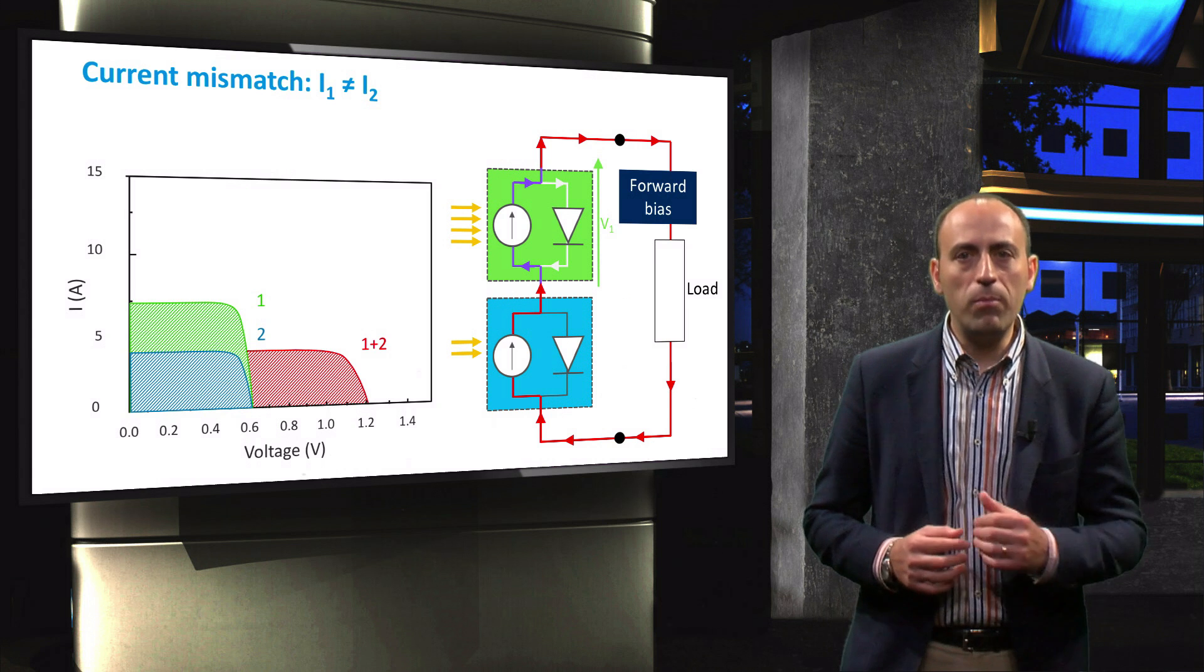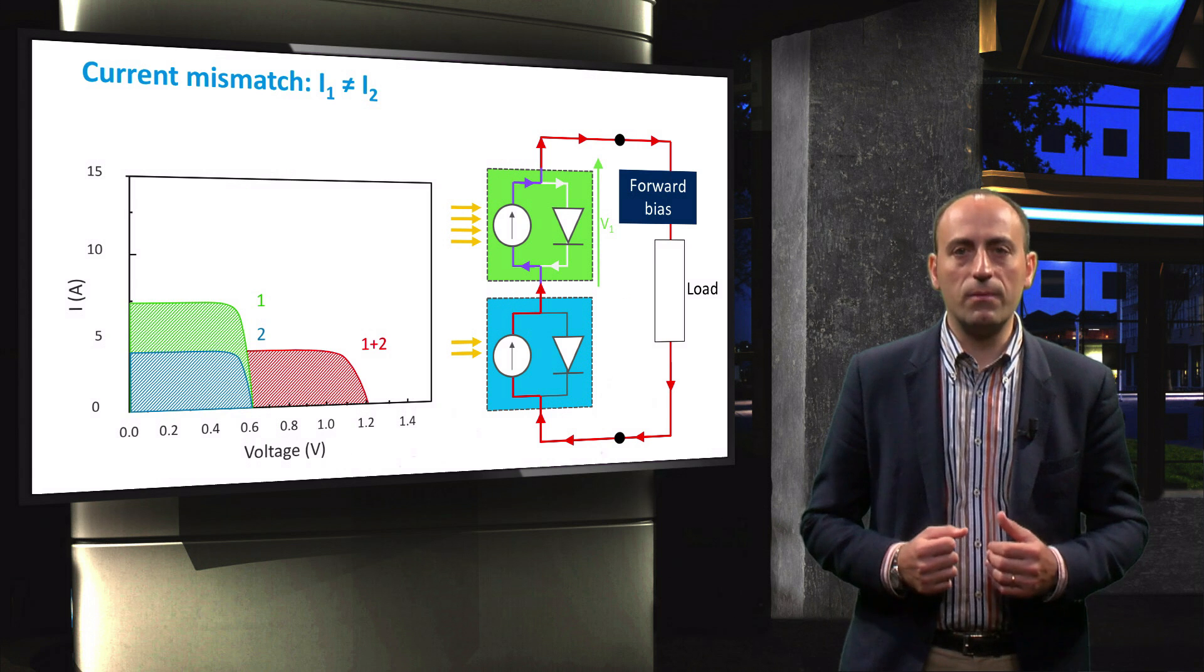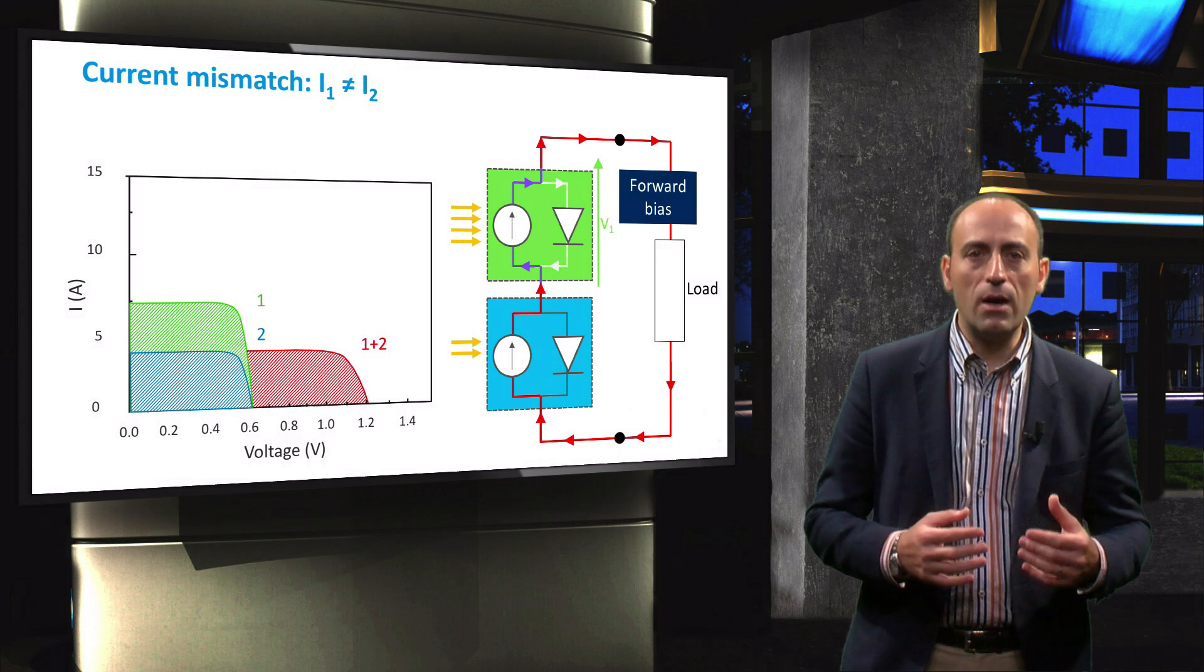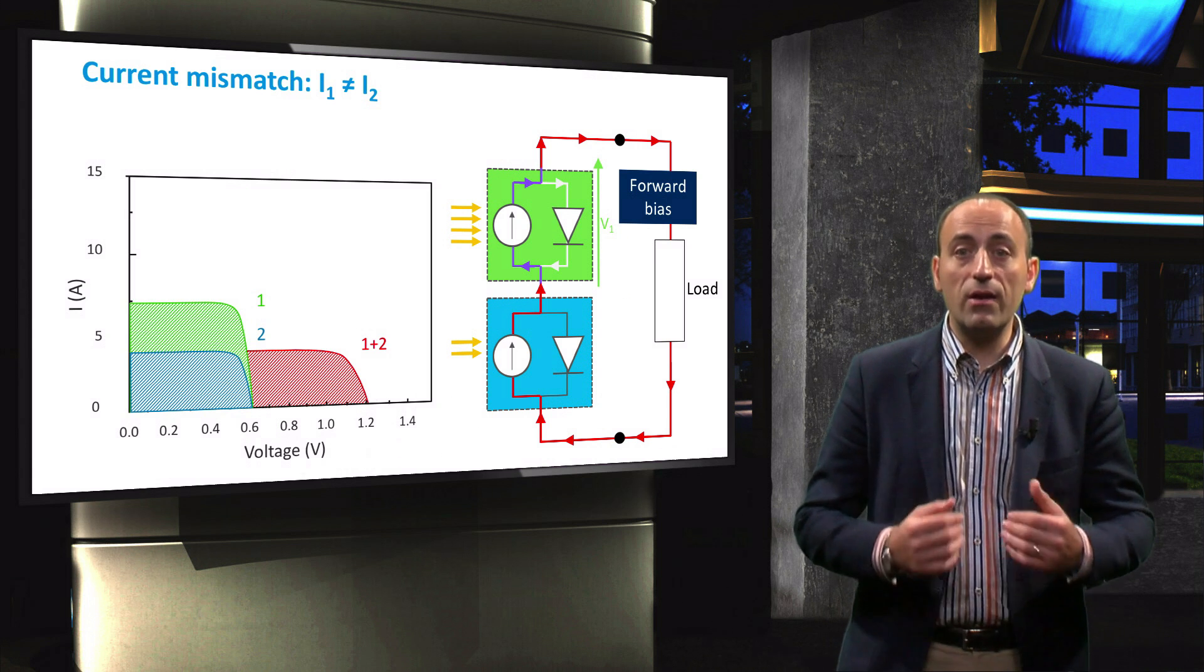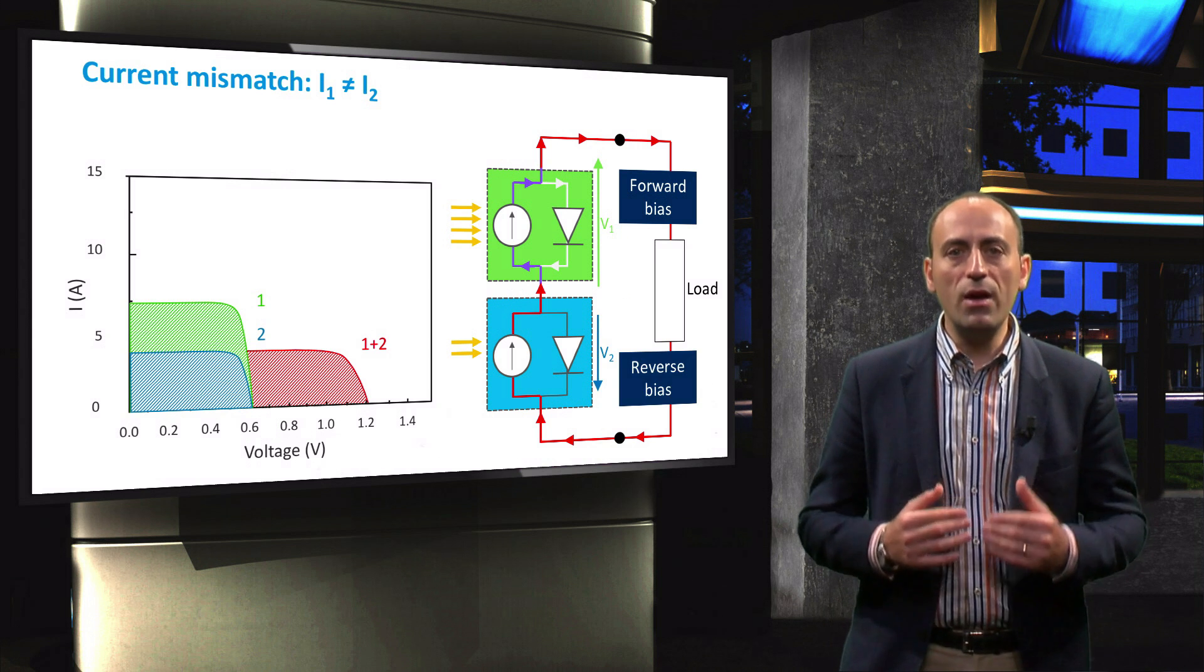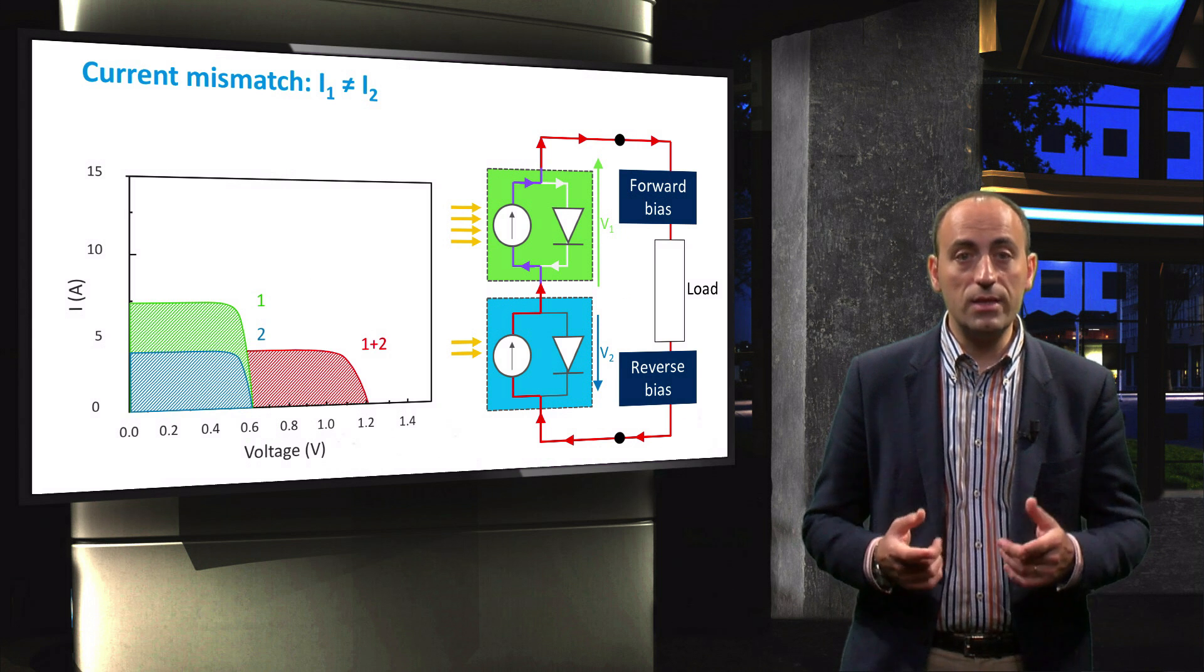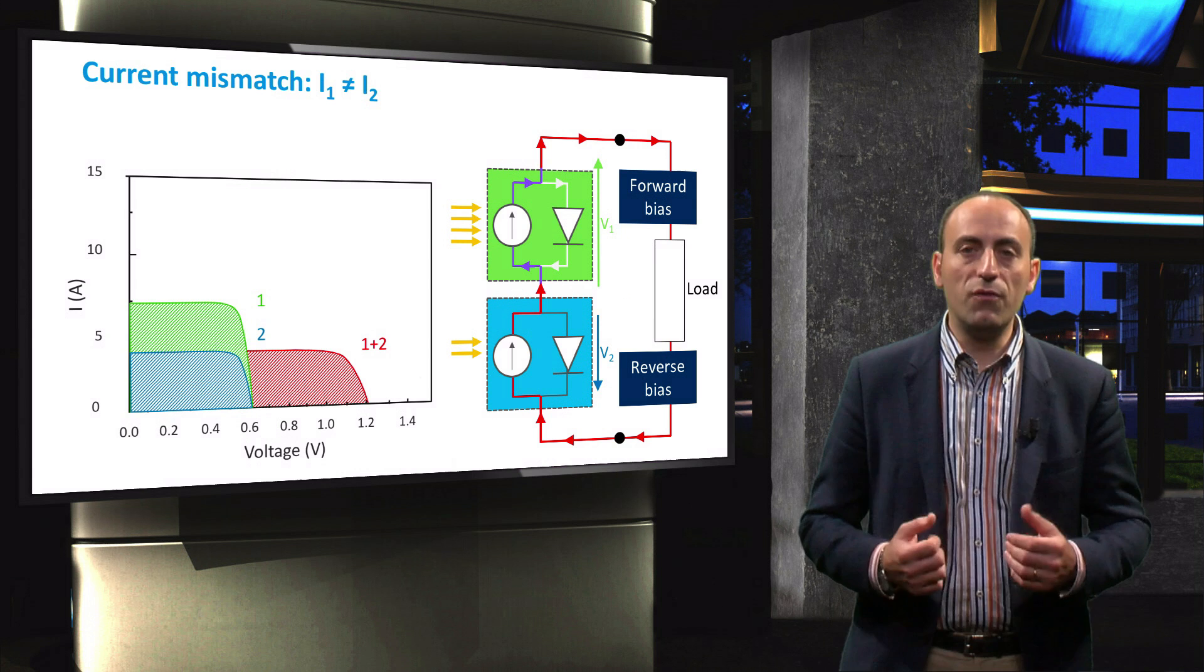Looking at the balance of voltages in this net, cell 1 will be forward biased, and since the low current cell number 2 is directly connected to the good cell 1, cell 2 becomes counter-polarized and therefore experiences inverse voltage. This means that the cell starts to dissipate power in the form of heat.